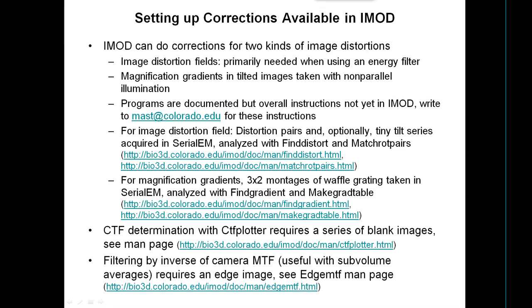There are IMOD corrections for image distortions that also involve some SerialEM use. One is image distortion fields — a set of vectors showing how the image has been displaced at various locations in the field — primarily needed when using an energy filter, particularly the GIF. The other corrects for magnification gradients in tilted images taken with non-parallel illumination. The programs are documented but the overall instructions haven't yet been integrated into IMOD docs — you need to write to request them.